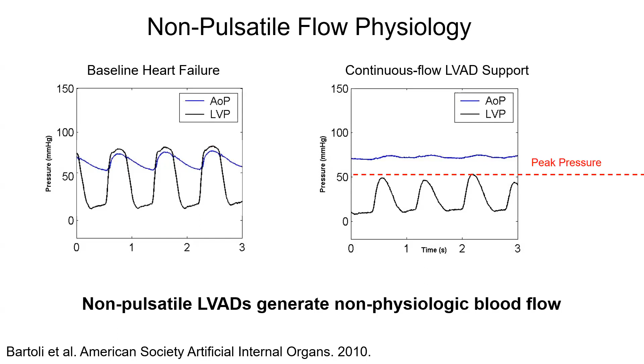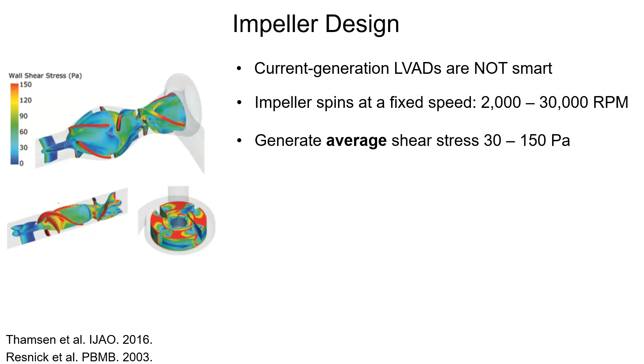The impeller is set at a fixed, very fast speed, anywhere from 2,000 to 30,000 revolutions per minute. As this impeller spins, it generates an average shear stress of about 30 to 150 pascals, and a peak shear stress of 1,500 to 3,000 pascals. It's important to note that normal shear stress in the body is 2 to 8 pascals. So these devices generate shear stress at least 2 orders of magnitude greater than normal physiologic values.